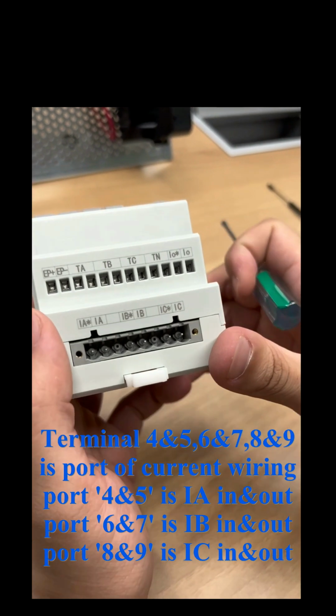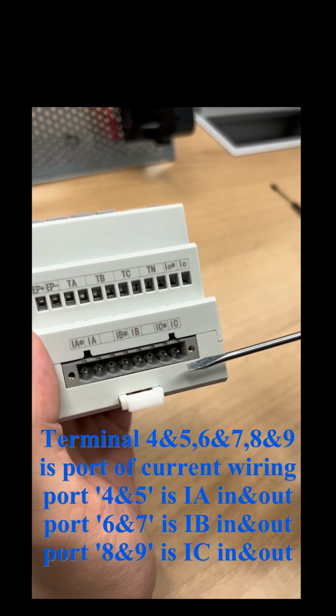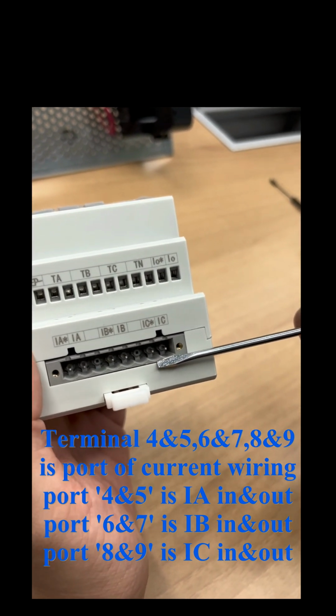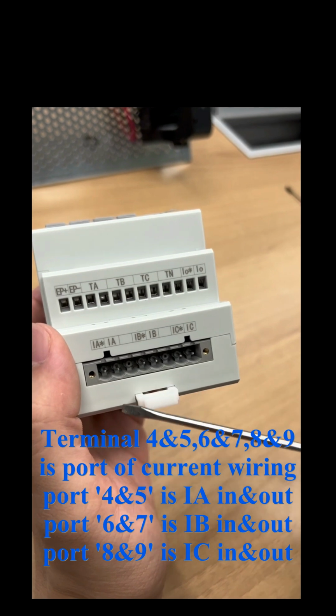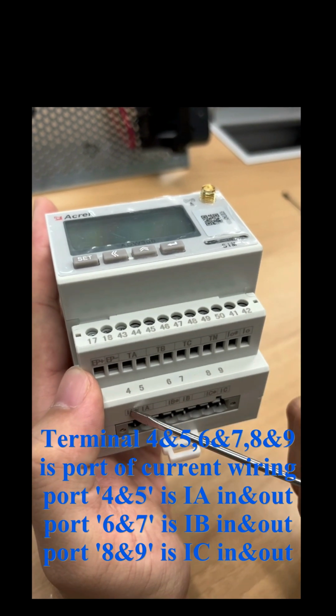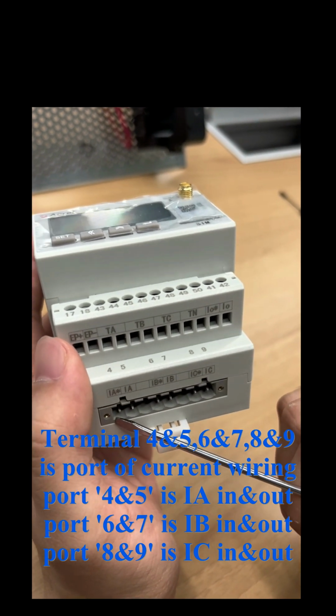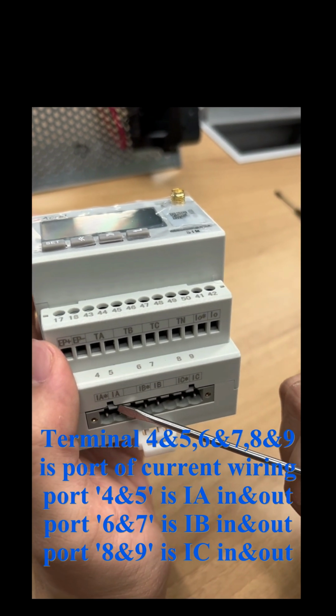Terminals 4 and 5, 6 and 7, and 8 and 9 are the current wiring ports. Ports 4 and 5 are IA in and out, ports 6 and 7 are IB in and out, and ports 8 and 9 are IC in and out.